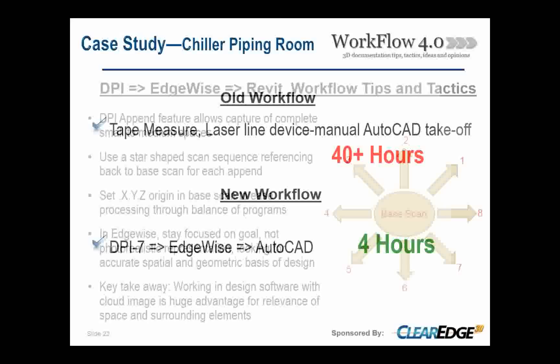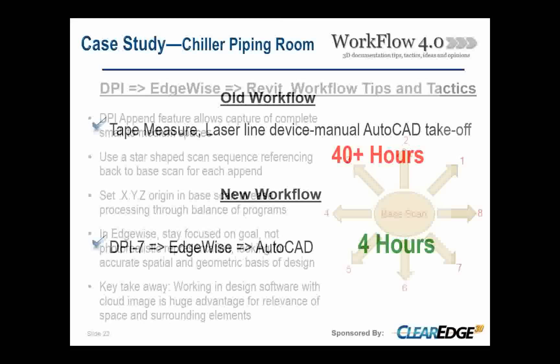Here in AutoCAD 2015 you can see the point cloud with the pipes resolved and brought in — these are the Edgewise pipes right where they were supposed to be after the cleaning process. Compared to the old method using a tape measure, laser devices, a digital camera, and a tablet — which probably would have taken 40 hours and multiple trips — with this workflow I completed it in a single trip in four hours. The quality is incomparable, and I still have all the extra surrounding data.